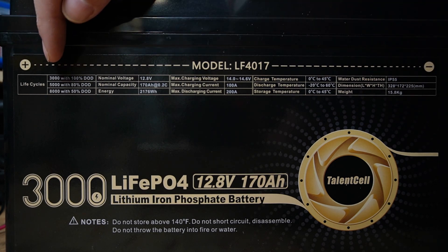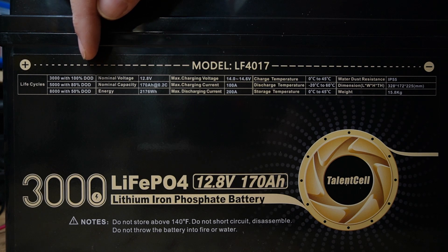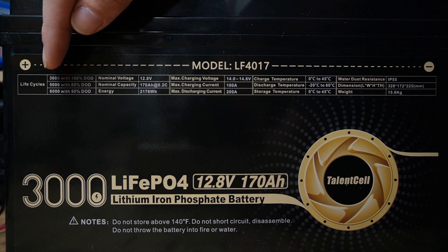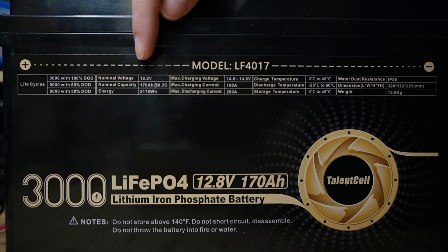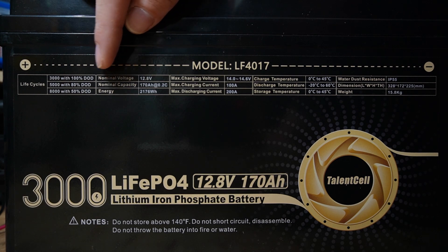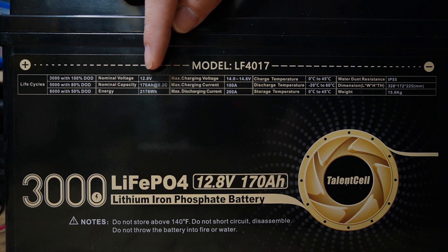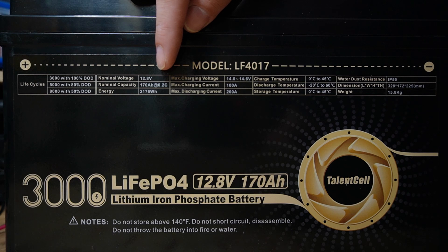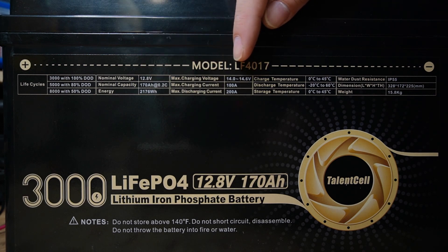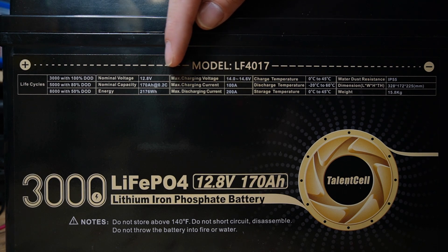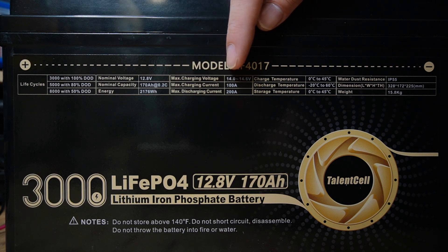We have 3,000 charge cycles with 100% depth of discharge, 5,000 with 80% depth of discharge, and 8,000 with 50% depth of discharge. Our nominal voltage is 12.8 volts, nominal capacity of 170 amp hours at a 0.2C discharge rate, and energy of 2,176 watt hours. Charging voltage is 14 to 14.6 volts, maximum charging current is 100 amps.